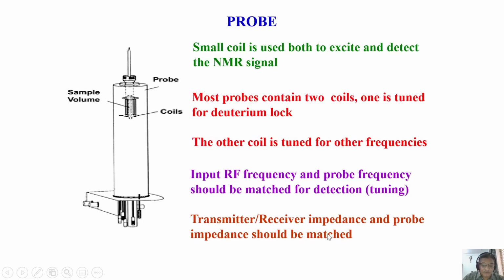Matching of the impedance of the transmitter and the receiver, matching of the input radio frequency with that of the probe frequency is a very important thing in the probe part. This is called probe tuning and matching. Both are done as soon as you put the sample, or when you want to see a particular resonant frequency of a particular nuclei. First thing is you have to tune the frequency of the probe so that you can transmit signal for that frequency and receive signal.